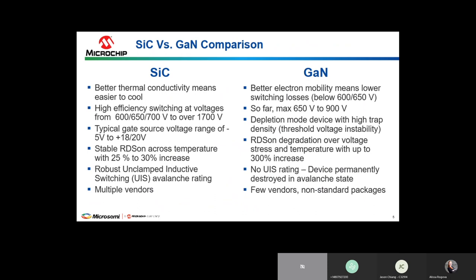Comparing with gallium nitride: below 600 volts, GaN is very competitive with silicon carbide in terms of performance — it switches a little bit faster and has slightly better performance and lower cost at those lower voltage applications. Above 600 to 650 volts, silicon carbide has much better performance, including a more stable RDS_on over temperature — its temperature coefficient is much less than that of gallium nitride.